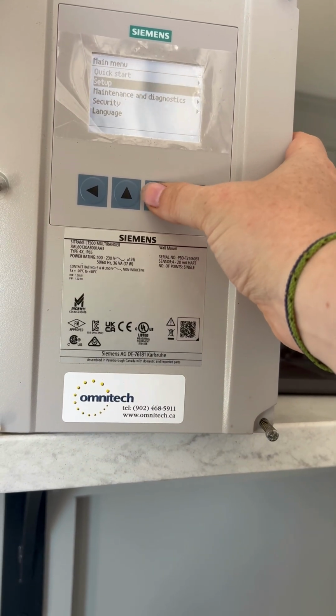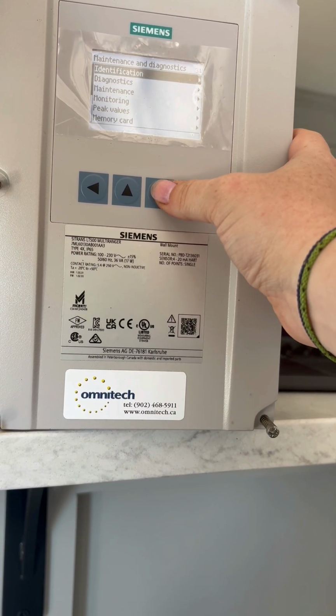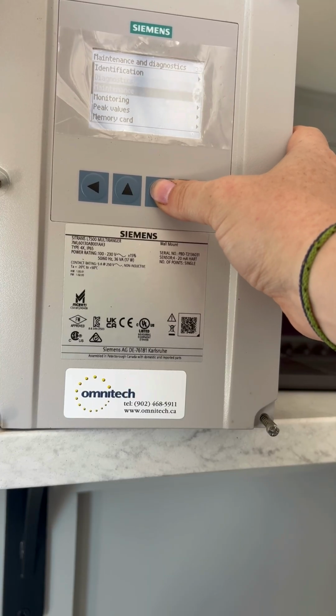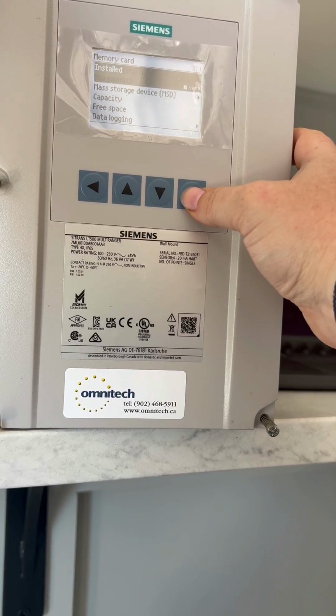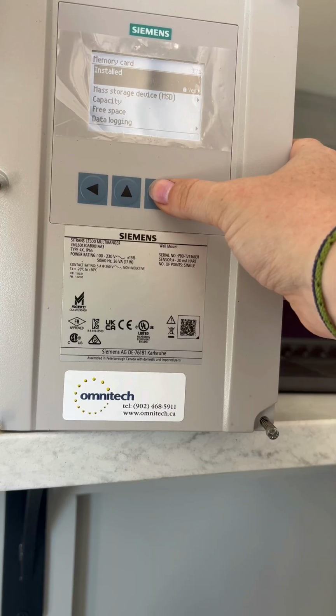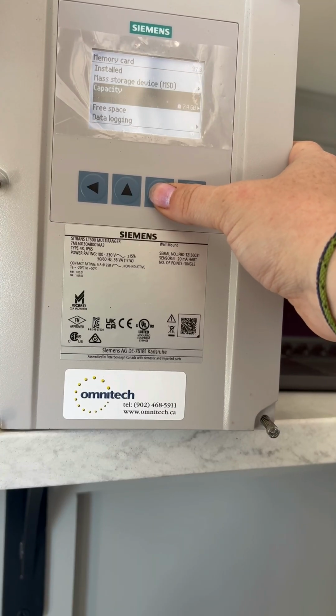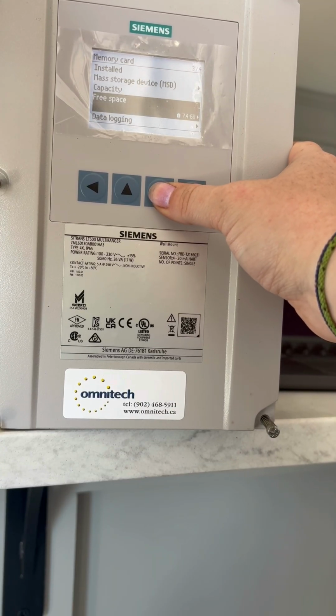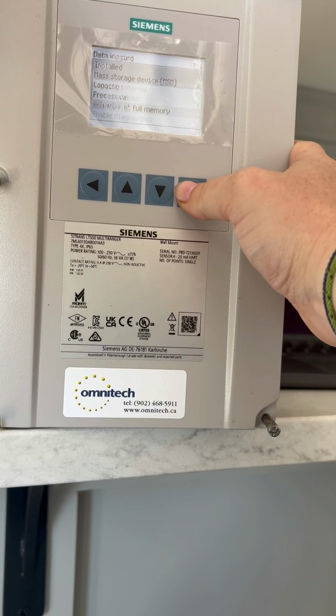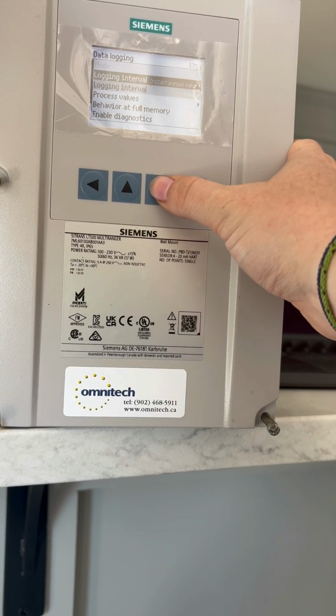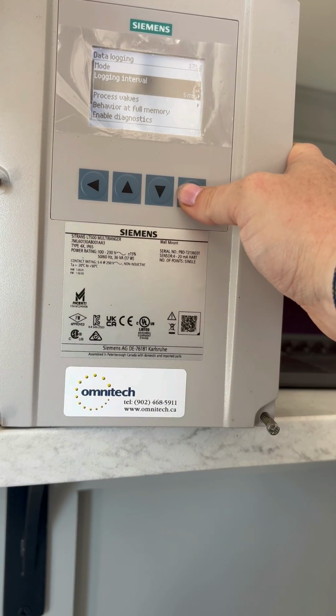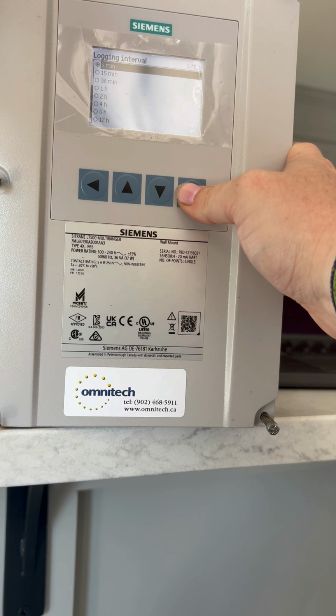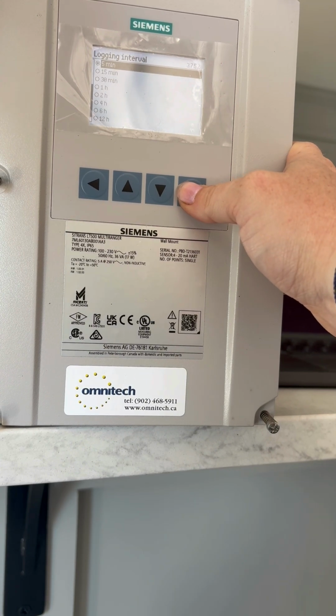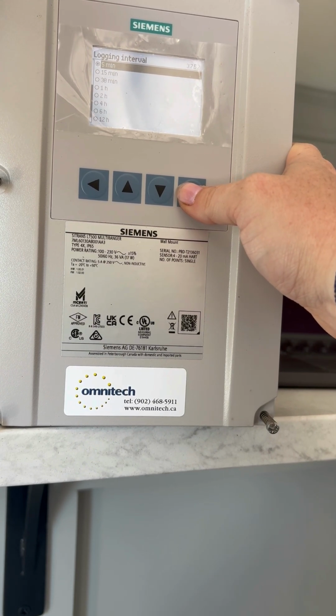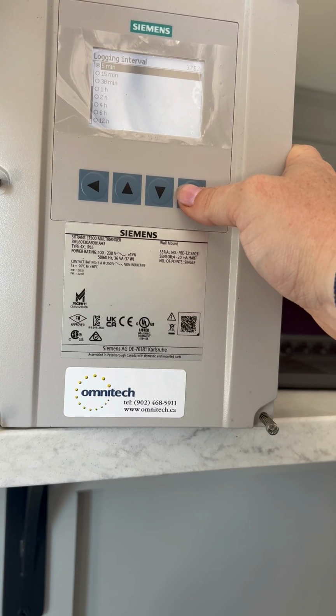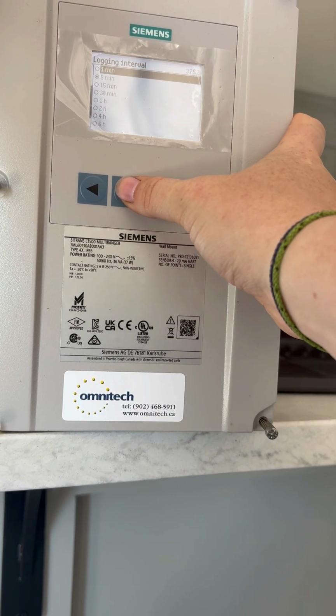The other thing, if you want to go into maintenance and diagnostics, if you go down into memory card, I have it installed. There's full capacity there, there's free space, and then you go into data logging. Basically what you want to check for yourself is how often you want to do that interval. The more often you do, the faster that card gets used up. But of course there's tons of space there and you're only logging like 1 or 2 values. So I have this set as 5 minutes.